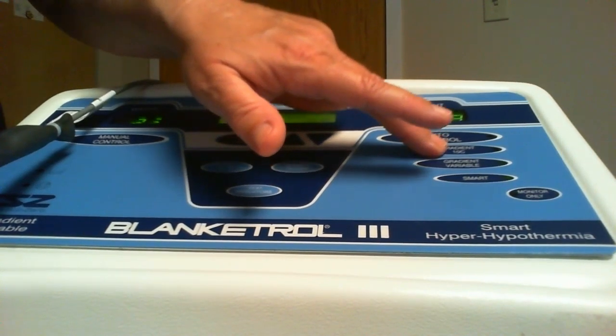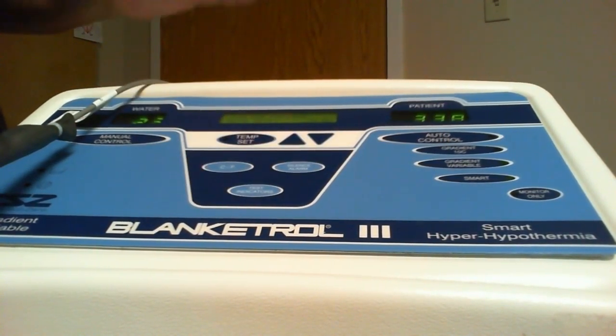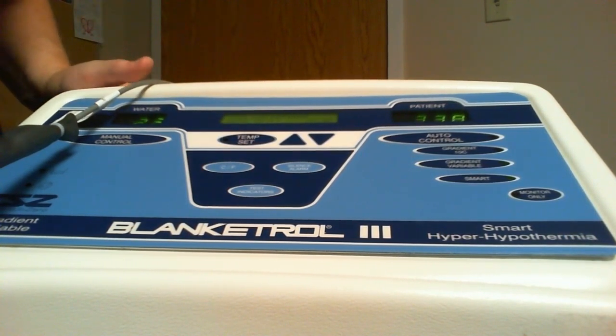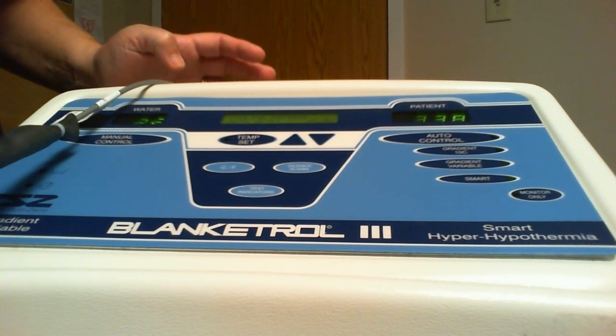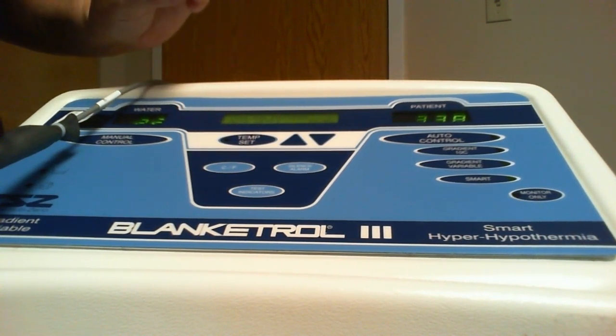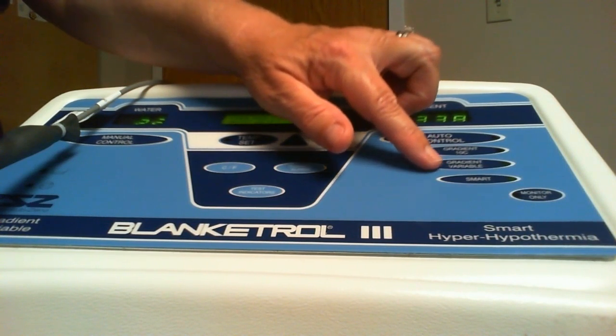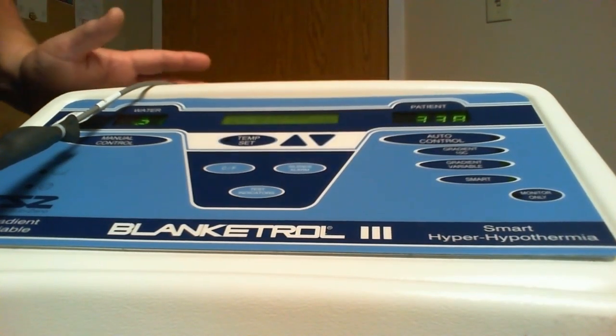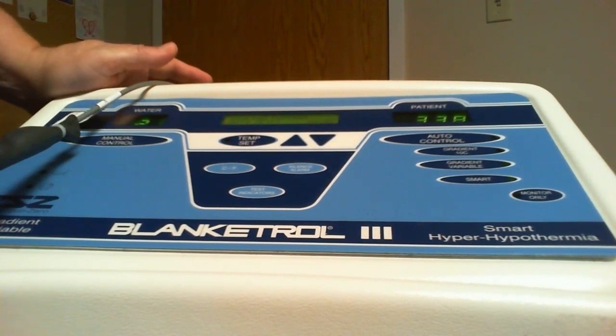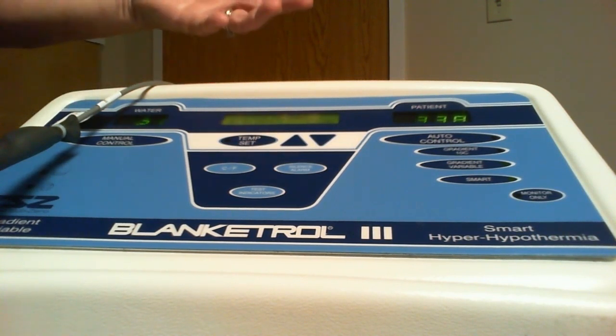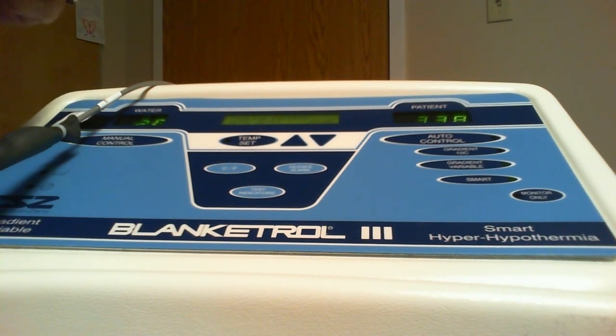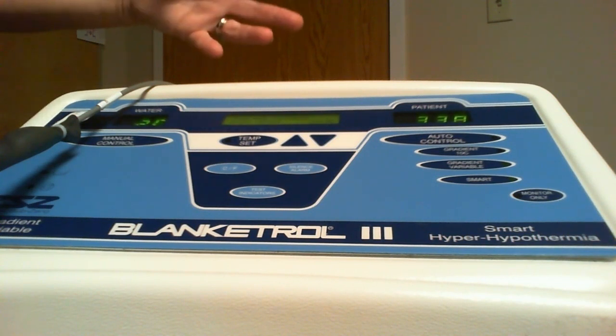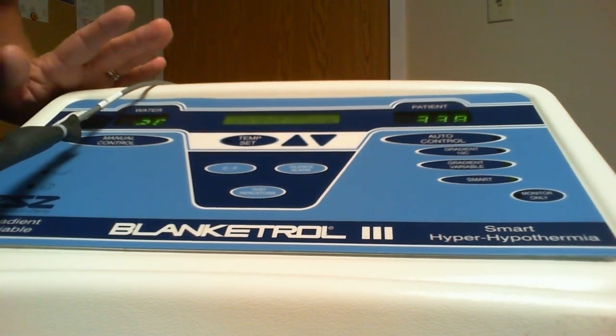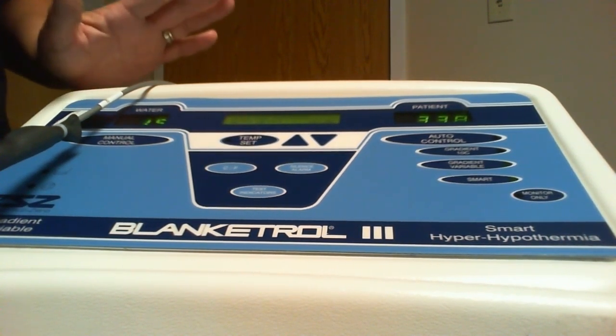So gradient 10 will be good for cooling most patients, but in those difficult patients who you're not able to maintain at target temperature, or maybe they are dropping, you could also change your gradient variable to 8 degrees. The company recommends that you do not set it any less than 7 degrees, just because we're surface cooling. We're trying to achieve a core temperature. Sometimes there is quite a difference between core temperature and what the surface is. And so 7 degrees is kind of the min that they want the gradient to be at.